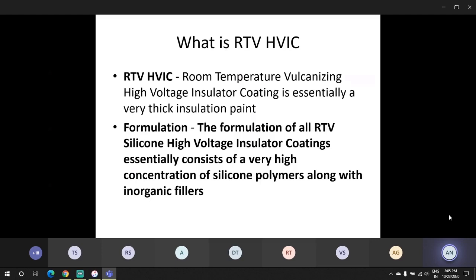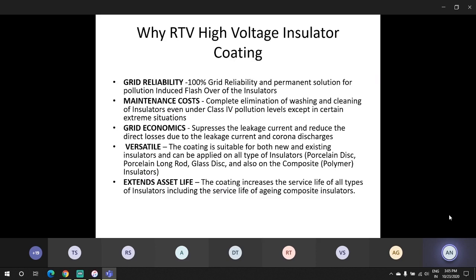What is RTV HVIC? It is basically a room temperature vulcanizing high voltage insulator coating. It is essentially a very thick insulation paint, and the formulation of all RTV silicone coatings essentially has a high concentration of silicone polymers along with some inorganic fillers. Why is RTV silicon high voltage insulator coating recommended? Because it provides you 100% grid reliability. The maintenance costs are completely reduced. It completely eliminates the washing and cleaning even under class 4 insulation pollution levels. It suppresses the leakage current. It also reduces the direct losses due to the leakage current and corona discharges.